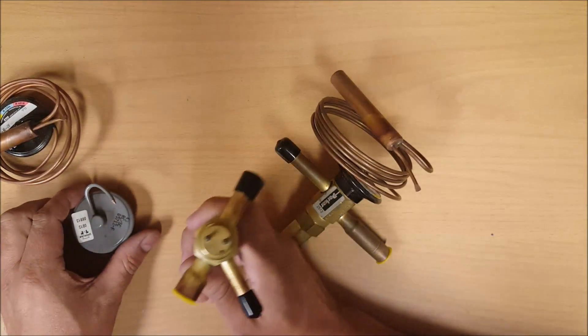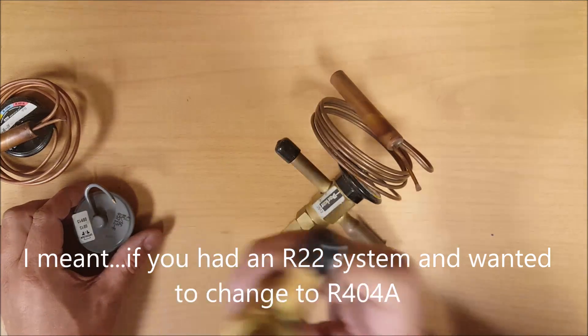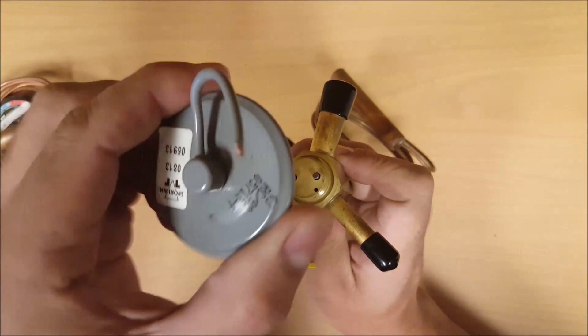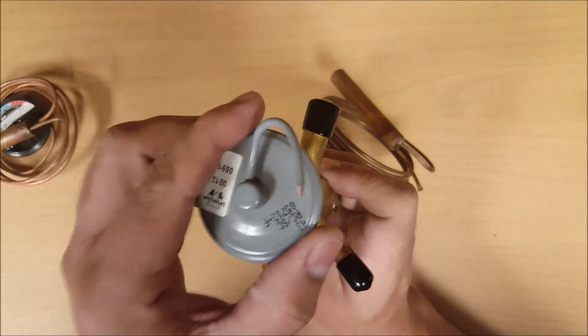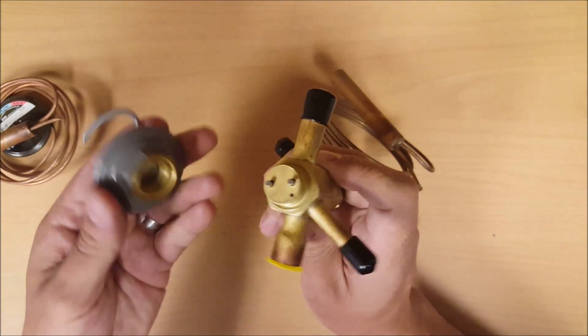Let's say you had an R22 system and wanted to change to R404A. You want to be sure to change out your power element that was rated for R22 to a R404A power element. Make sure you do that.